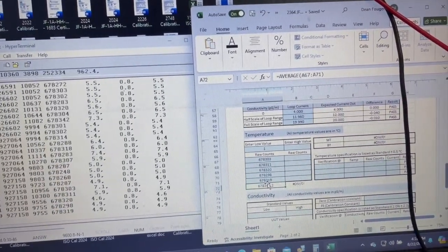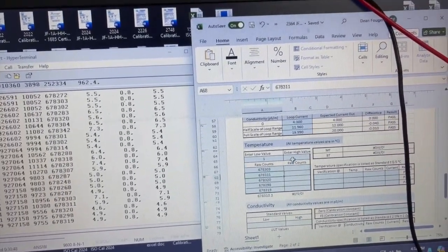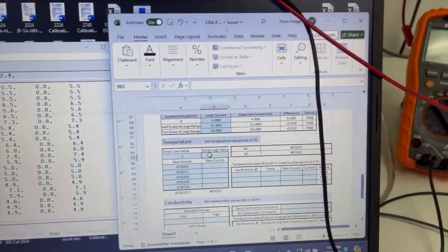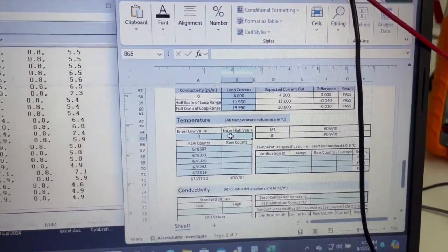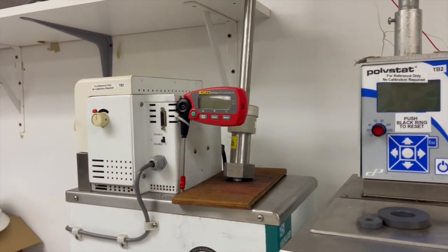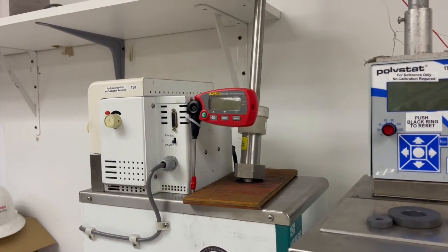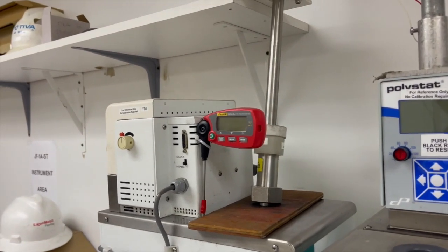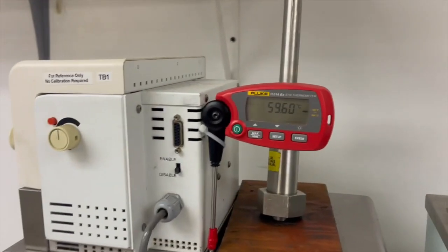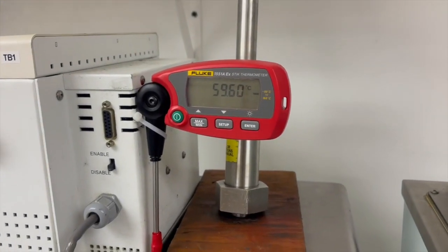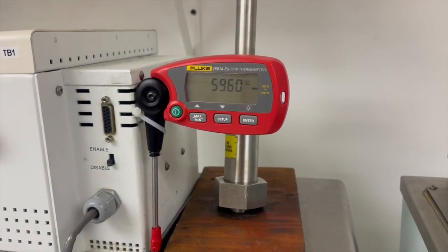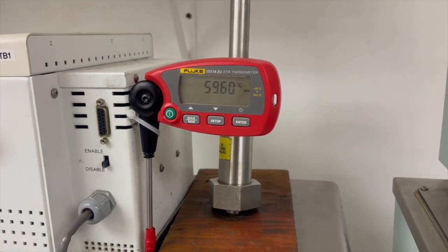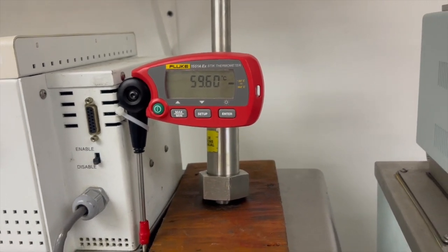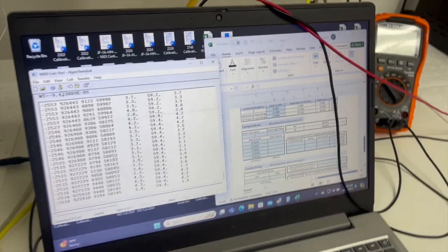The bottom there is the average. And now we're ready to get the high value in order to get our MT and BT values. So we gotta take the sensor out and change the bath over to 55 degrees, which gets it to about 59.6 degrees.